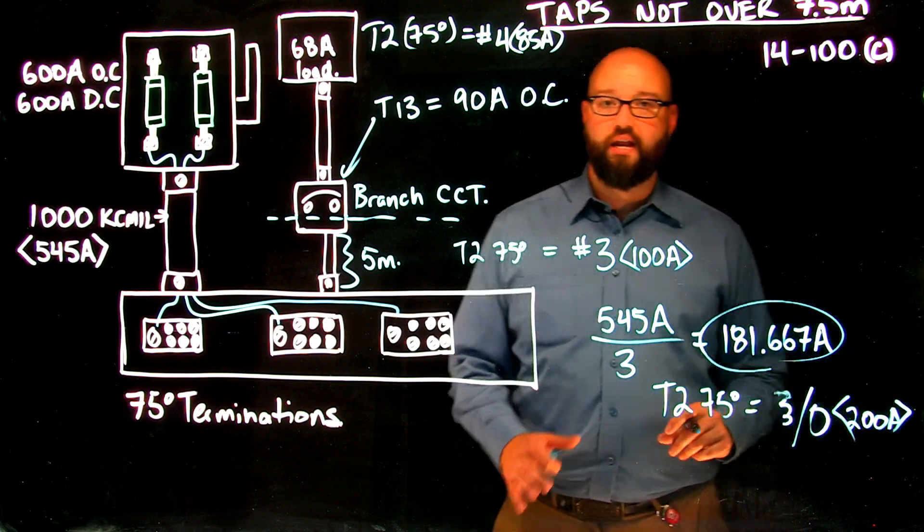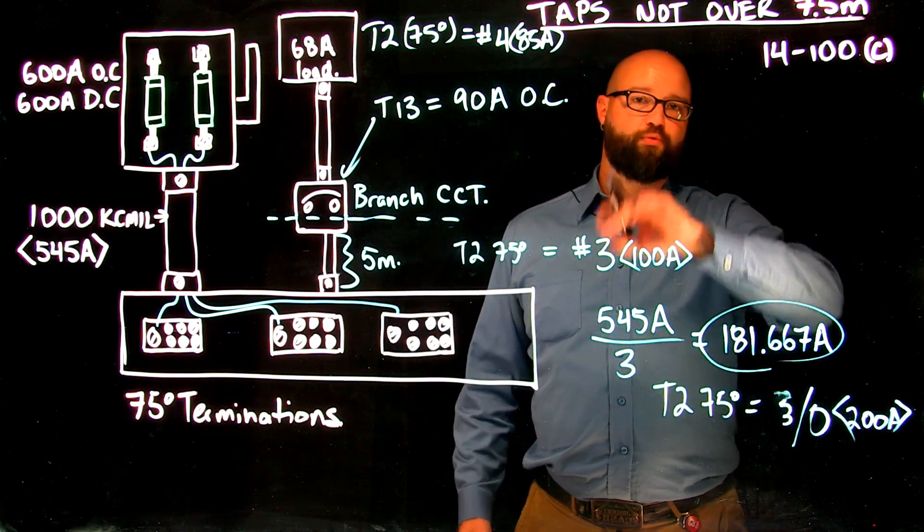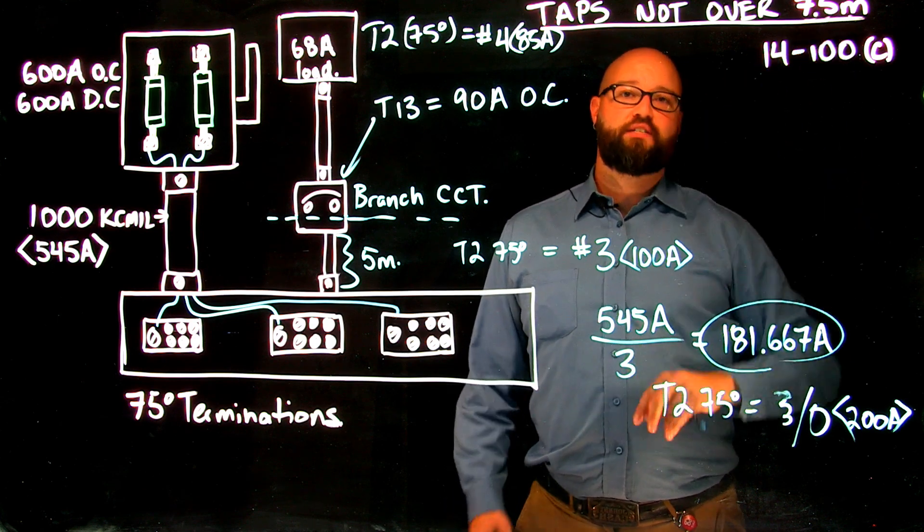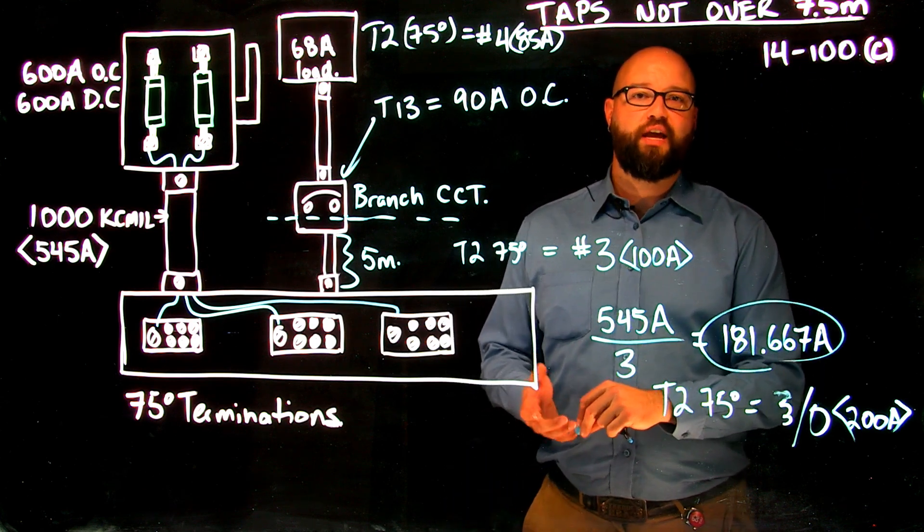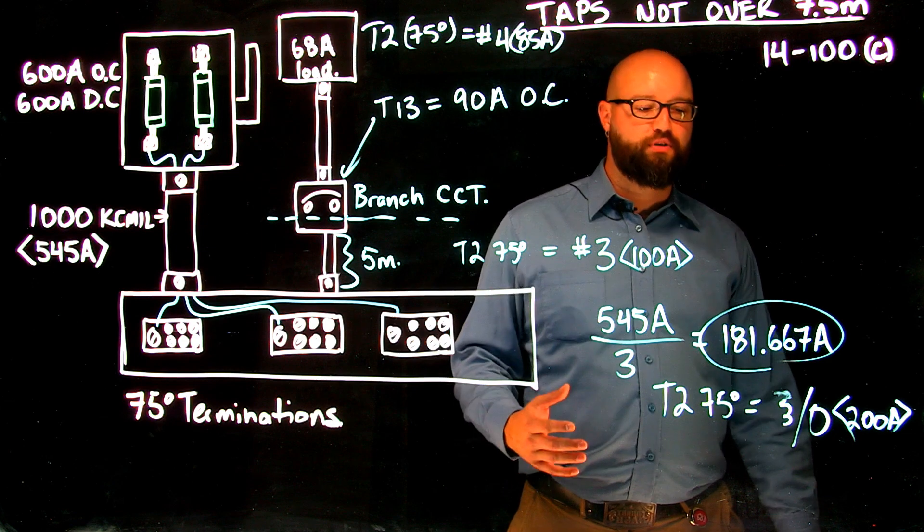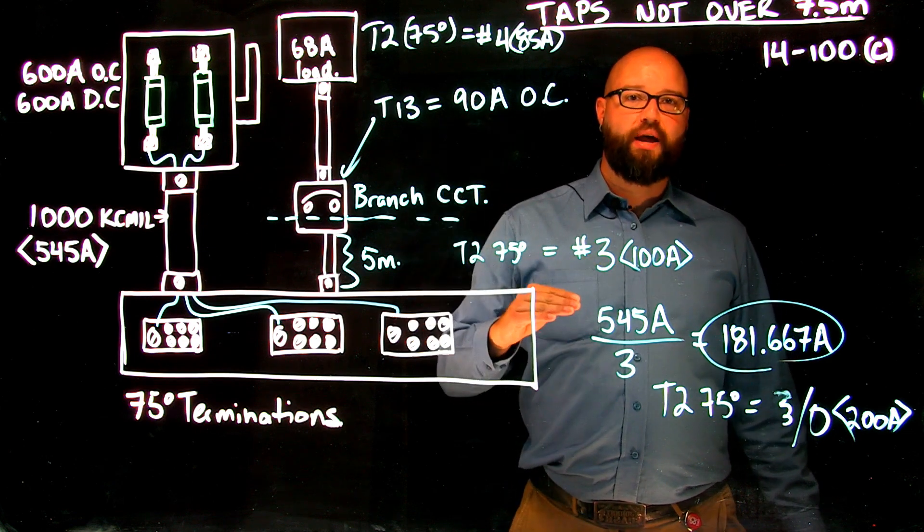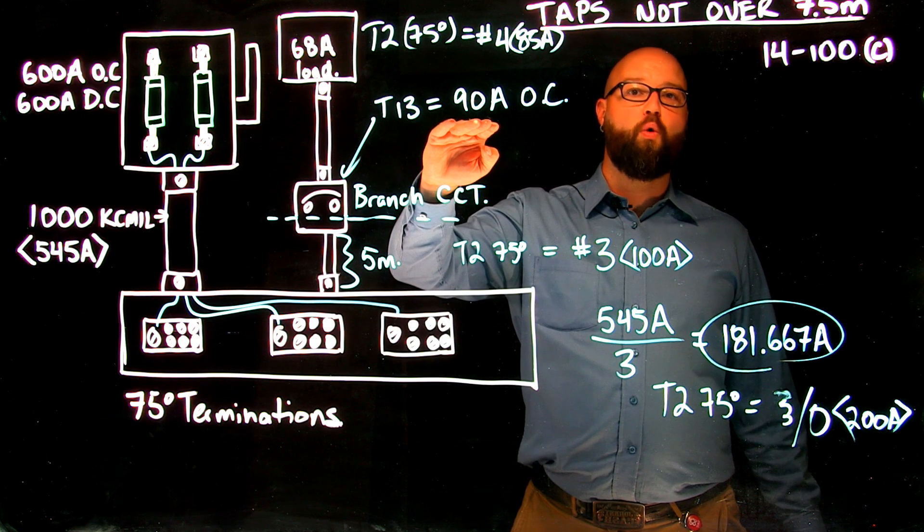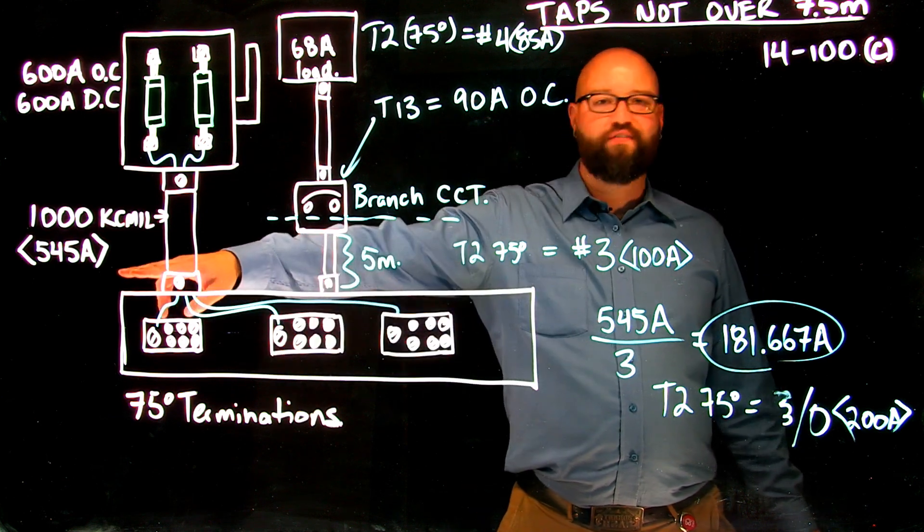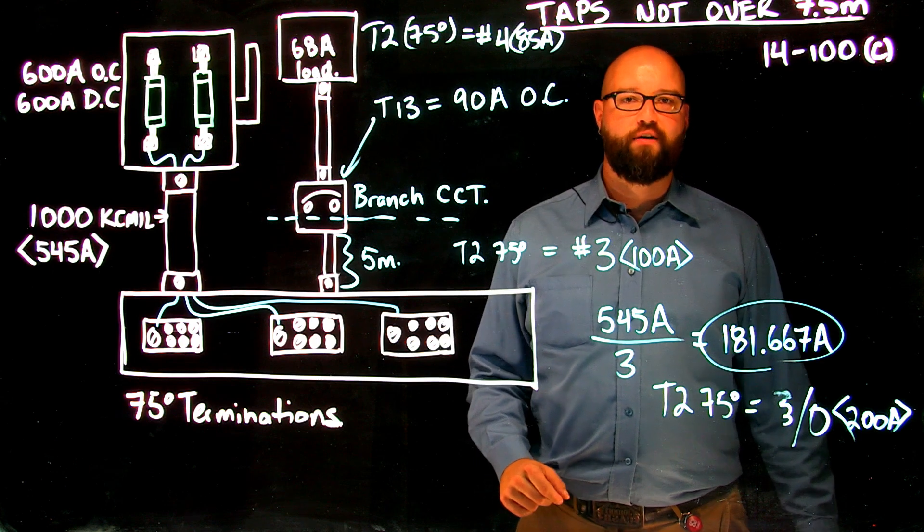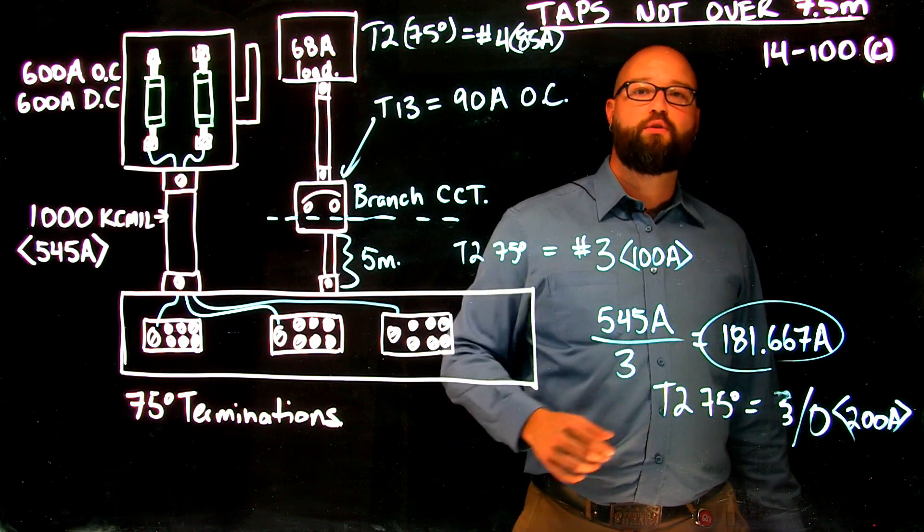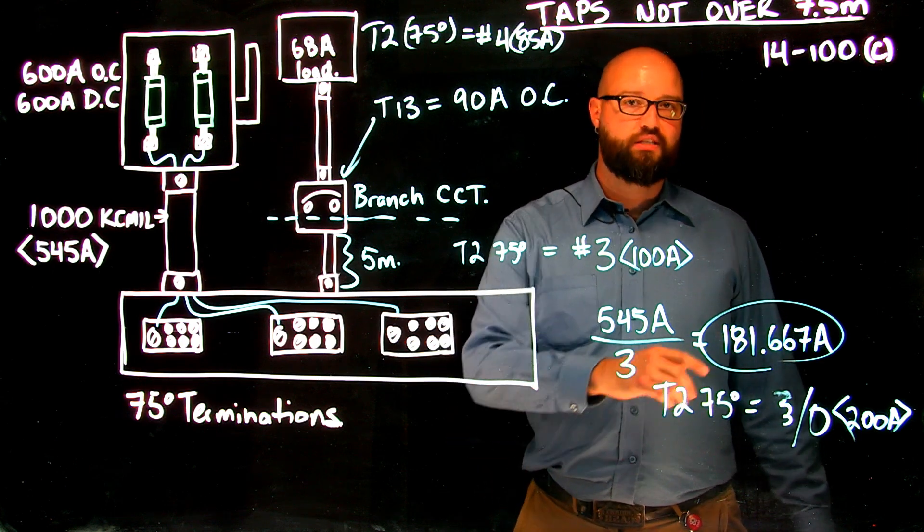So again, when we're selecting a tap conductor that's greater than 3 meters but does not exceed 7.5 meters in length, we have to make the choice between our tap conductor based off of being larger than the ampacity of the overcurrent it supplies or one-third the ampacity of the feeder conductor, whichever is the larger of the two, which in this case wins. Not always the case, but in this case it does.